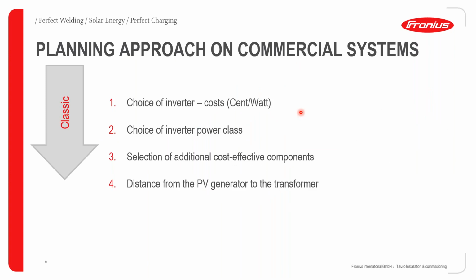When you're planning your commercial systems, the classical approach normally is to look at the choice of the inverter, and here we are talking about the cost of the inverter per watt. Then we also consider the choice of the inverter power class. Also important is to look at the additional cost components or cost-effective components that can be coupled to such criteria, as well as the distance from the PV generator to the transformer.